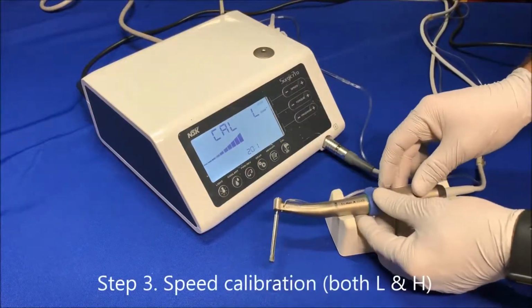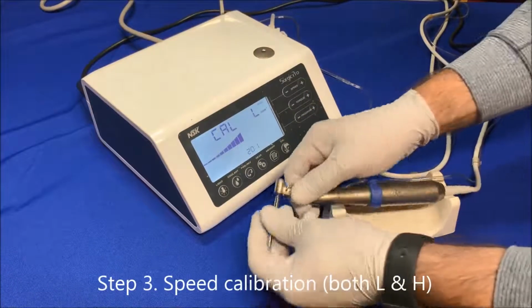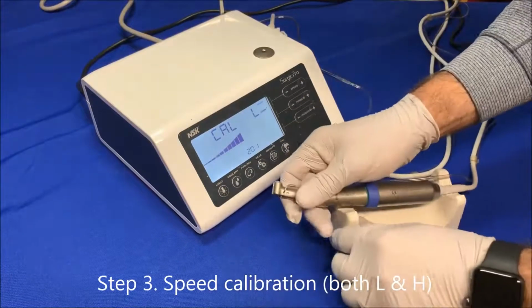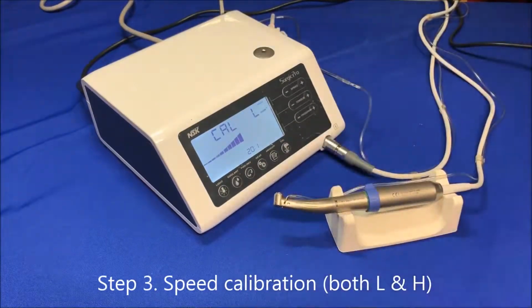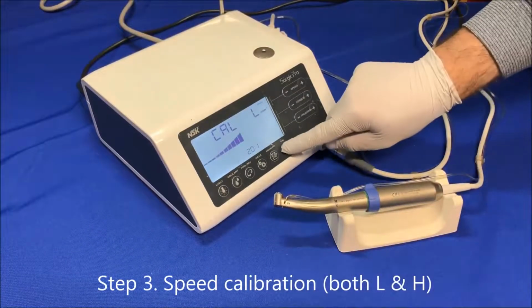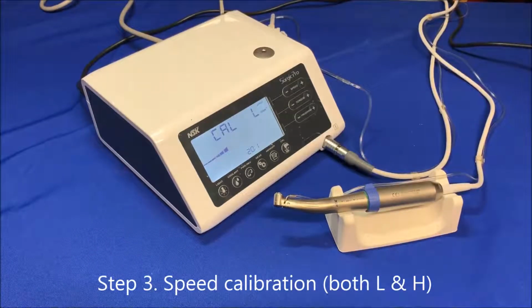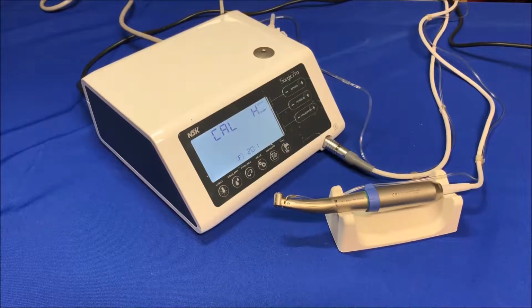Speed calibration. Remove the drill and leave the motor and the handpiece on the handpiece stand. Press the calibration button. The attachment will start working and rotate with no drill, of course. 8 seconds in slow, another 8 seconds in fast speed. Once this part is completed, there will be a beep sound. That's when the entire process is completed.